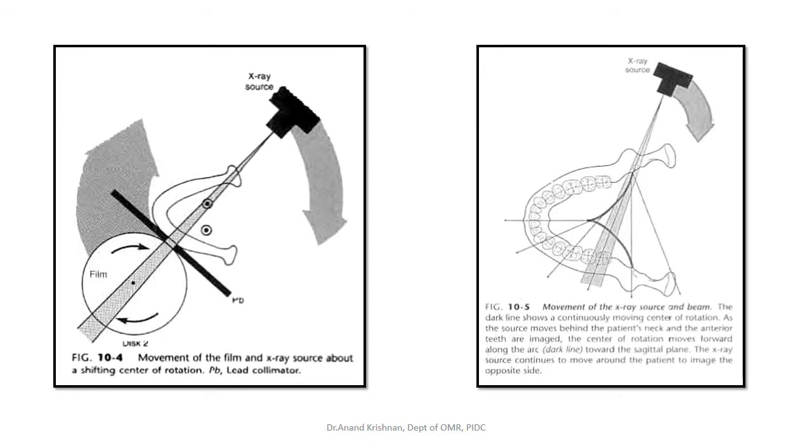The flat panel sensor is tuned in such a way that constantly while it gets exposed, it will take the image, transmit it, take the image, transmit, and it happens in millisecond variation, so that there is no lag and you are able to get the sequence of images very clearly, whereas in film it has to be manually moved.